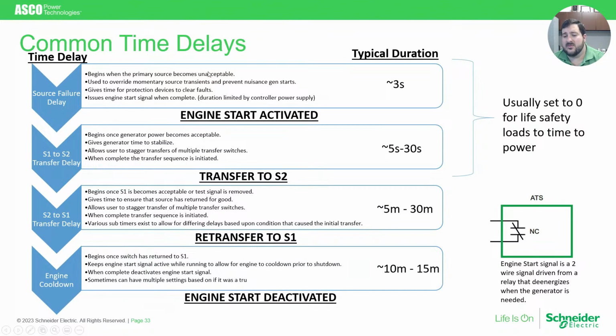We don't immediately start a transfer. So the first thing that happens when, say, a blackout happens, is there is a source failure delay to make sure the source really did fail. If there's a transient or a short circuit that is pulling down the voltage, we want to make sure that if it's somewhere else in the system, the breakers have time to clear that fault, or if it is a momentary transient, that it can resolve itself before you nuisance start the generator. So we wait a short time delay before starting the generator.